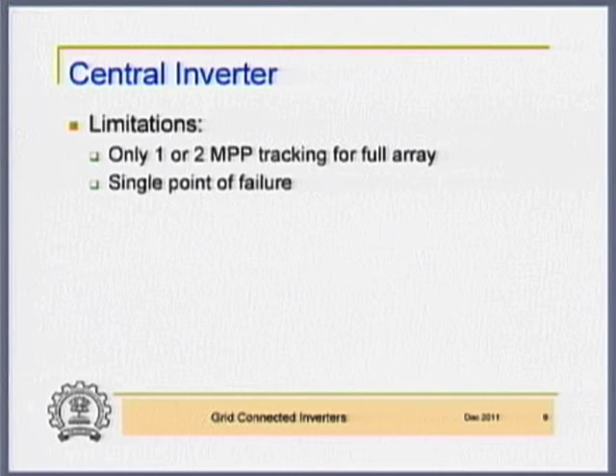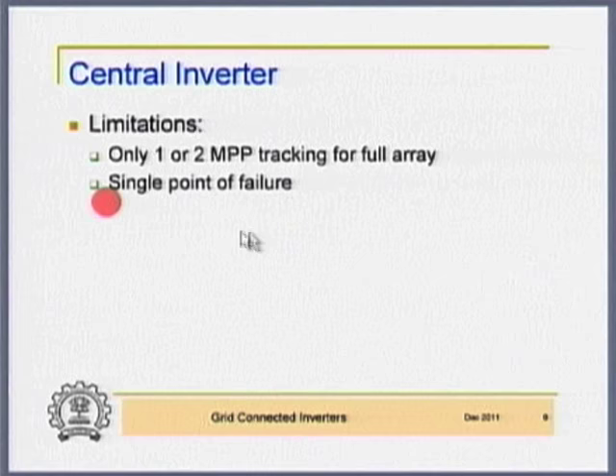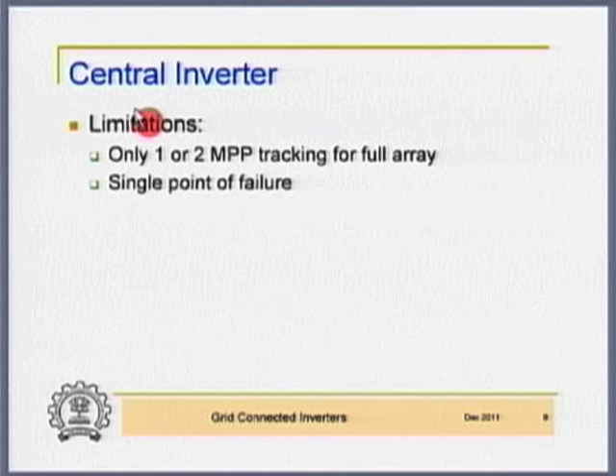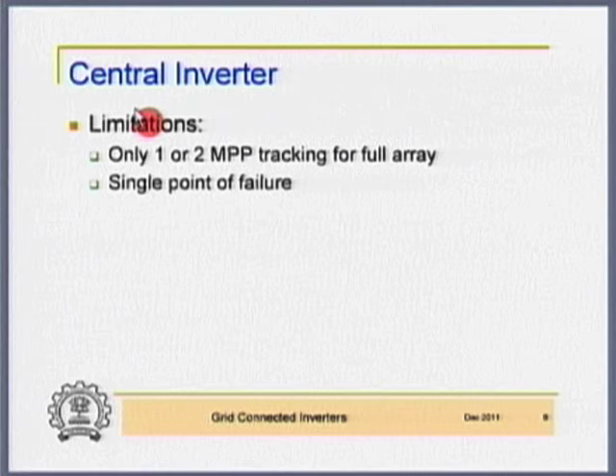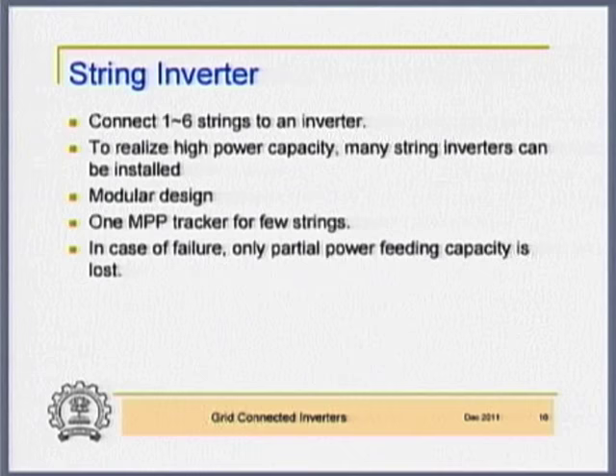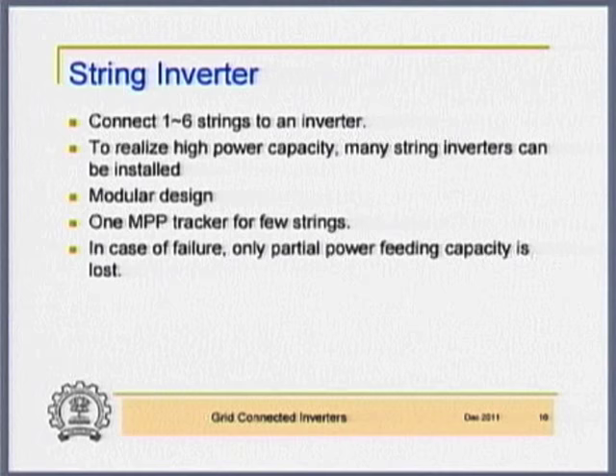What are the limitations of the central inverter? Only 1 or 2 MPPT algorithms are used for the full array — panel-wise MPPT may not be possible, so it may not be possible to handle shading and other issues. Regarding reliability: it is a single point of failure. If the inverter fails, the entire power is being handled by that inverter, so there is no power transfer at all.